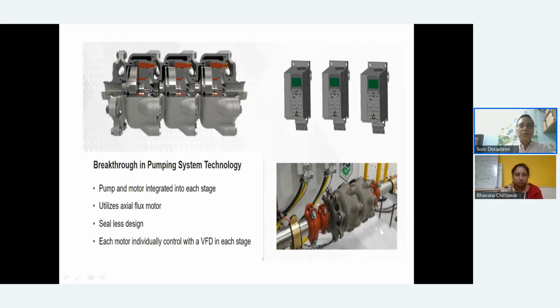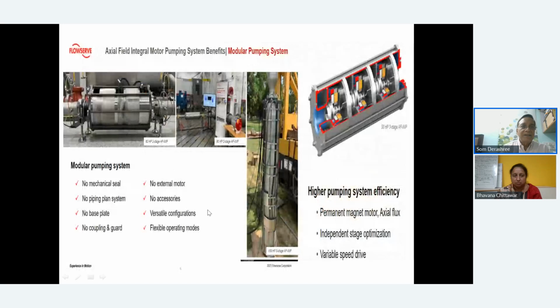This is actually a pump and motor built into a system, and these are all in series. So there is a single shaft, they are all axial flux, and each is an independent module. Now it will be just pipe in pipe, just like this. There is no foundation required, nothing. You can just plug it in like a pipe in here. These are some pipe-in applications. Each one of these stages is independently VFD driven. The pump and motor are together, and of course it is like a submersible pump. So the motor is already cooled by this.